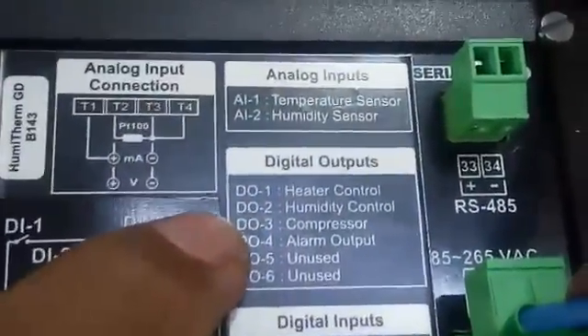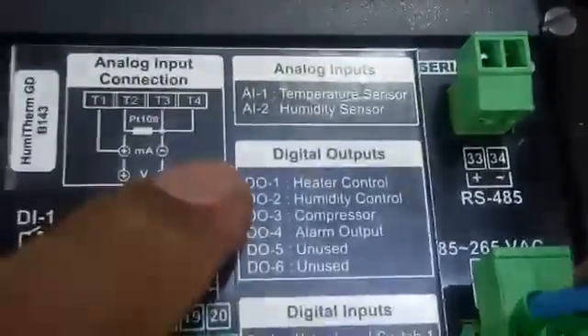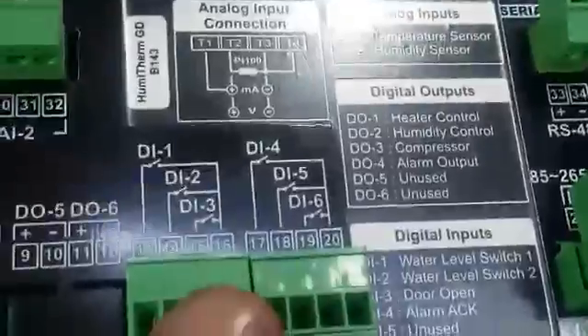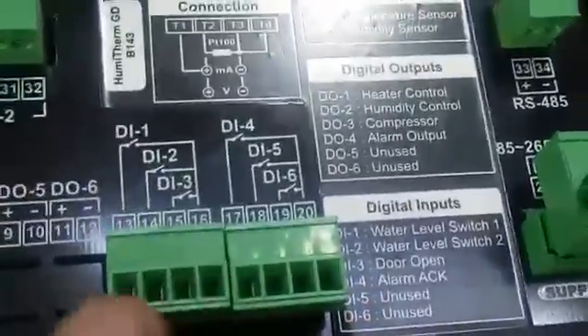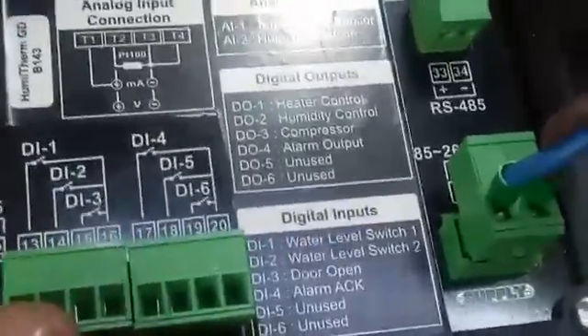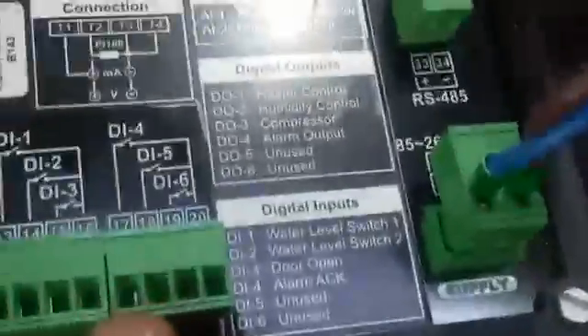This is the heater, humidity control, compressor, and alarm output. Here you can connect the heater — DO1. For humidity control, you can connect DO2. These two only are required. For any other output, like door open signal — if you want to connect it, the door open signal will come from here. If you want any alarm acknowledgement signal, you can connect it to DI4.